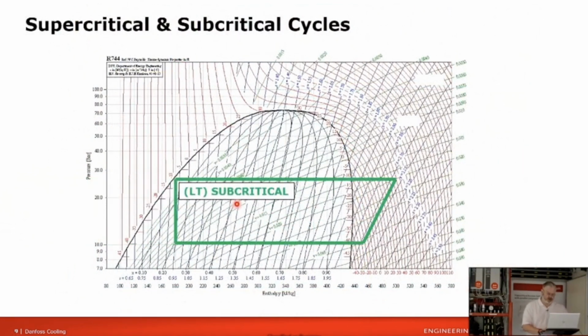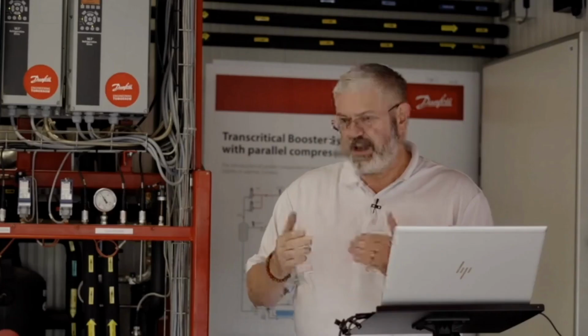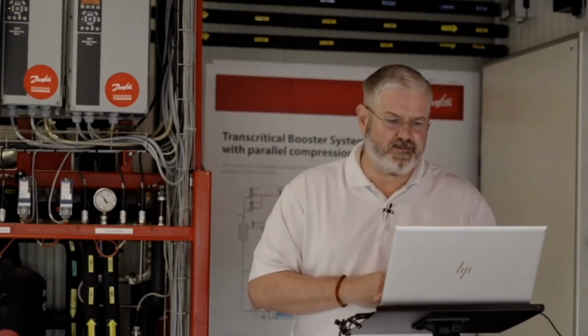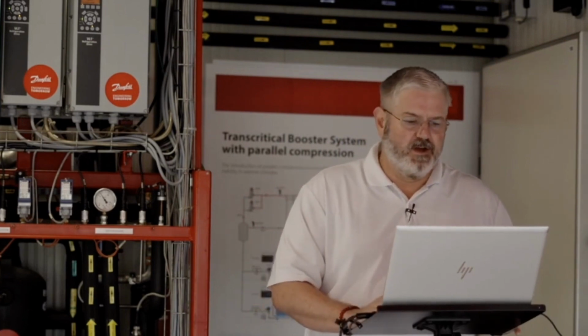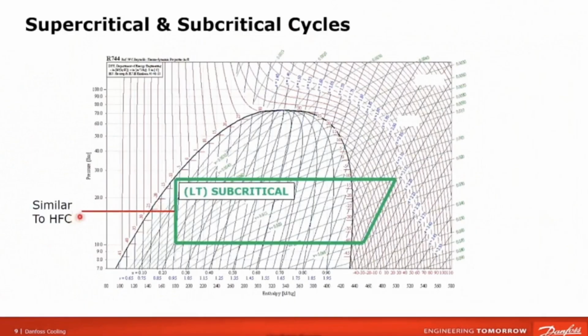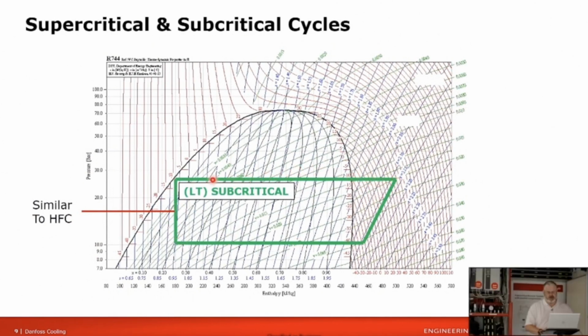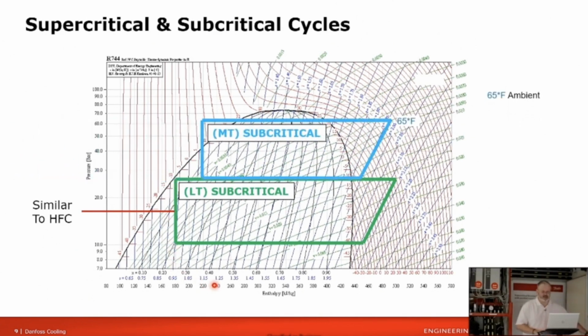So I mentioned what's similar to HFC and what's different from HFC. The low temp portion of a CO₂ system, what they'll call a booster system, we don't have on our unit. Our unit is only medium temp for cost reasons and such. We didn't include low temp loads. But the low temp side of it is similar to HFC in that the high side happens all within the dome. So if you think of this and reference it to the HFC, you would see desuperheating, and then you're in a liquid state by the time you go back to the expansion valve, as well as on the high side of a medium temp transcritical system in a low ambient.